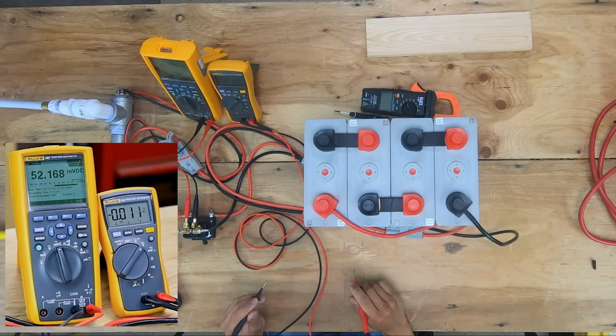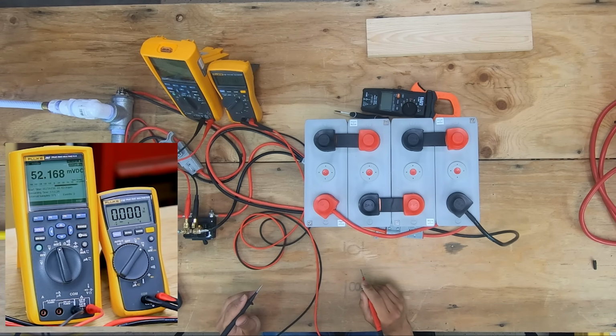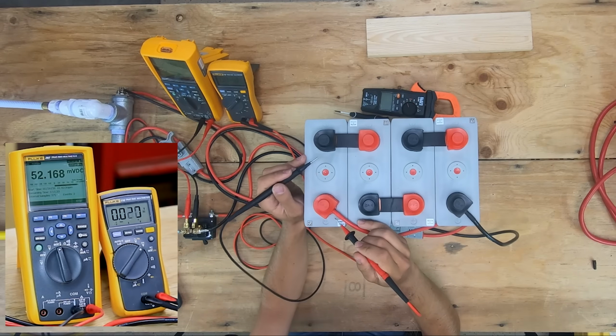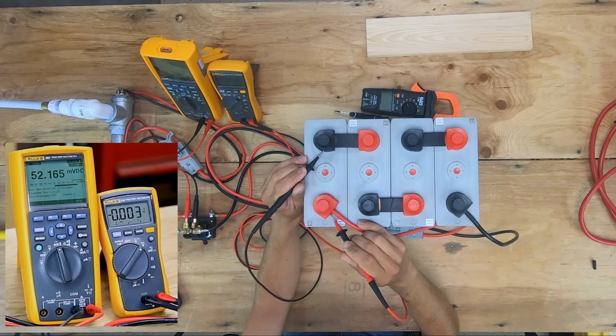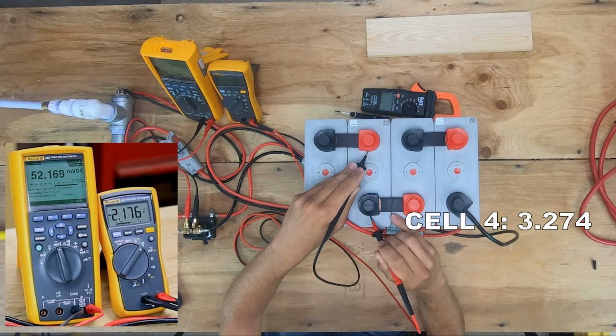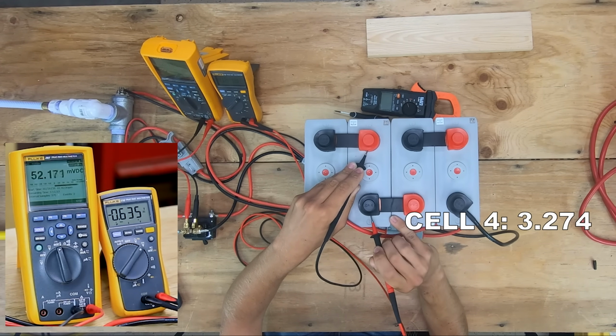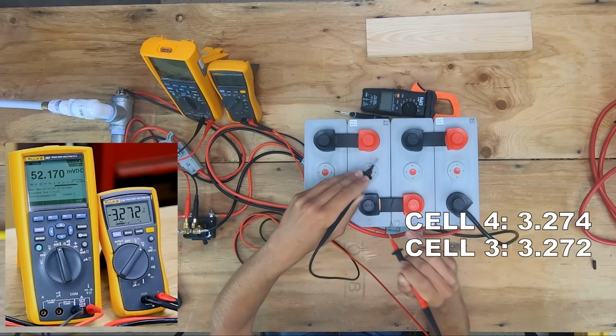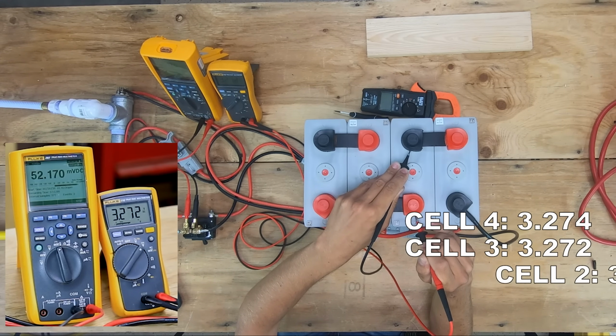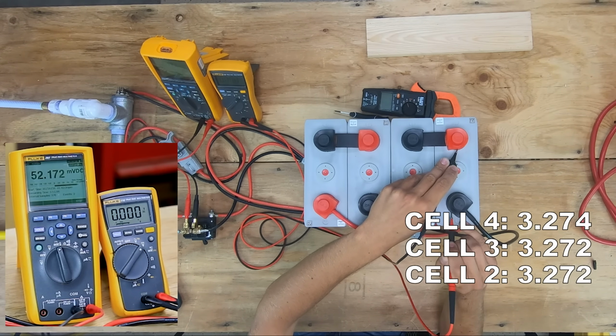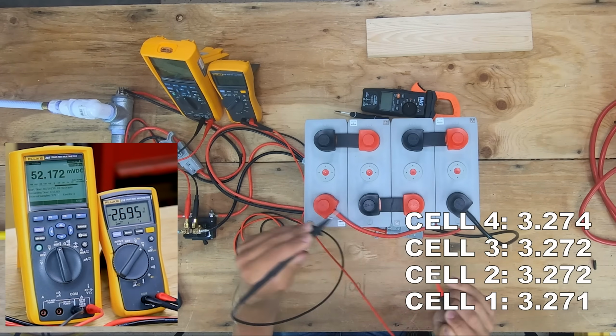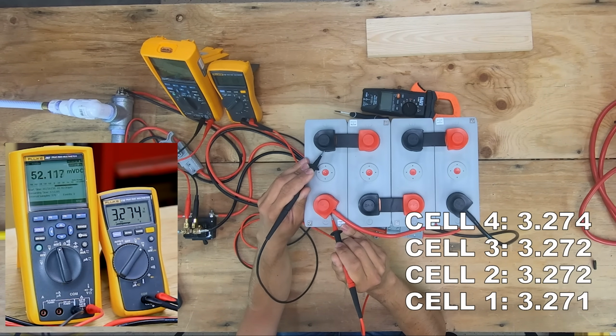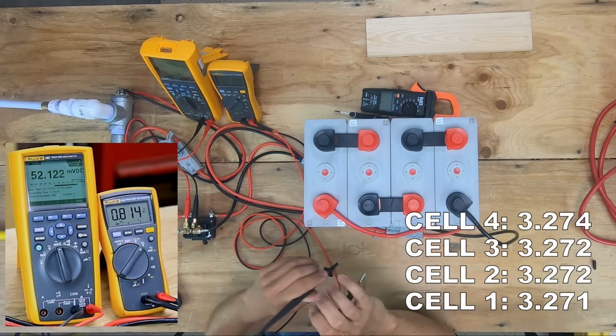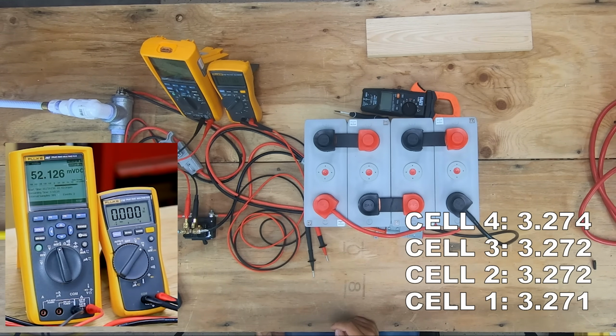We're currently drawing 52.16 amps, and I'm on sample 370, with 5 hours and 11 minutes remaining time on the measurement. But what's very interesting is if I probe cell 4, I have 3.274 volts. Cell 3, 3.272 volts. Cell 2, 3.272 volts. And cell 1, 3.271 volts. Going back to cell 4 to check for drift, I have 3.274 volts. So these batteries are all within 3 millivolts of each other.